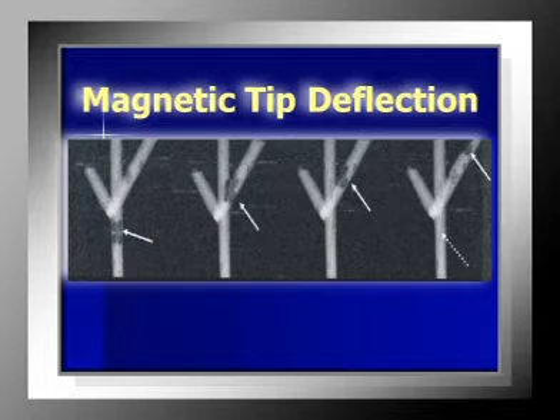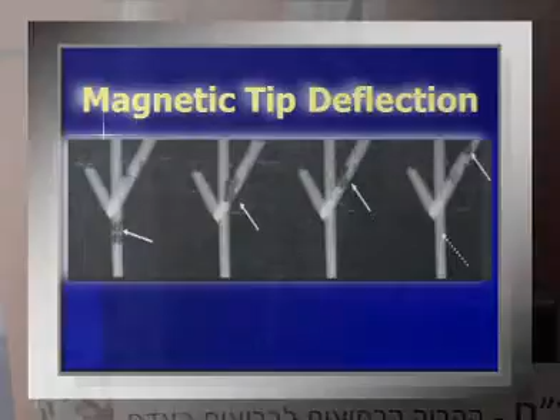So that way, this would allow very, very accurate manipulation of the catheter inside the MRI scanner to be done automatically. So there could be pre-programmed sequences as to where you wanted the catheter to go. So whether you're working in the brain or the heart or even in the abdomen, this magnetic tip deflection could allow very accurate and very reproducible movement of the catheter. So then electrophysiologists have to be able to make electrical recordings during imaging. And this just shows you that, in fact, even when there's 8 or 10 kilowatts of radio frequency energy being applied to the body in order to get MR imaging, you can actually measure millivolt signals in the heart.